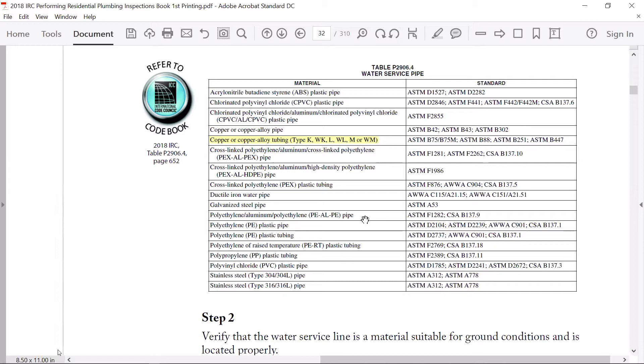Well, let's see, going off memory, it has something to do with the thickness of the pipe, right? Yes, it does. Absolutely. It's the wall thickness of the pipe. So type K, if you're taking notes, ladies and gentlemen, is the thickest wall copper tubing. Type L is your next one down, and then type M is your thinnest that's allowed to be used.